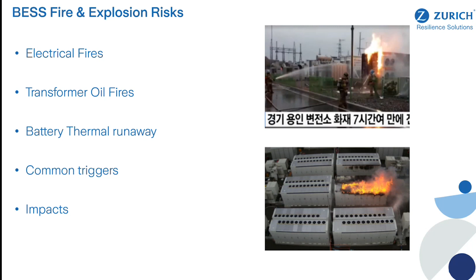So what's the impact? Well, to start off, a fire that can be very difficult and challenging to put out. Explosions can happen, as a buildup of flammable gases could occur inside these battery containers. And then we've got environmental issues, because the chemicals released if a fire does occur are not particularly pleasant - hydrocarbons, hydrogen fluoride, hydrogen chloride, all possible chemicals that could be released in the event that one of the containers does actually catch alight.